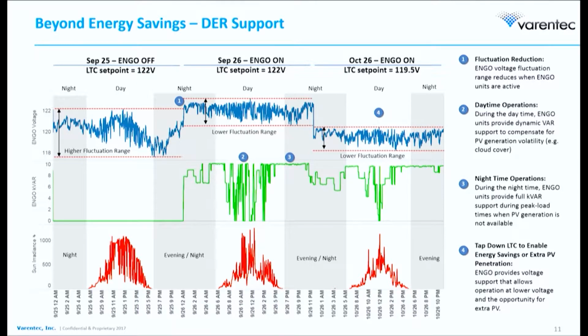Let me explain these lines. The first line is the actual voltage observed at the monitored locations. The second line shows how much VARs it's injecting — without getting too technical, if it's at 0 the unit is passive, doing nothing, and as it goes up to 10 it's fully engaged, doing its best to push the voltage up. The third line, in red, is the solar irradiance in that area.